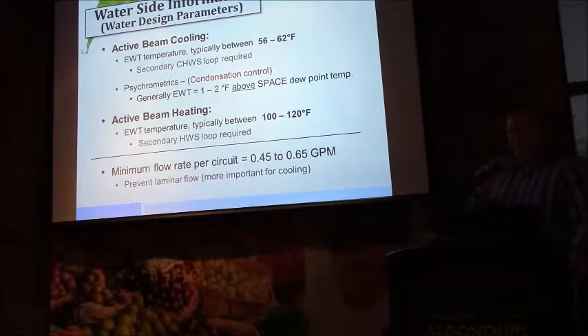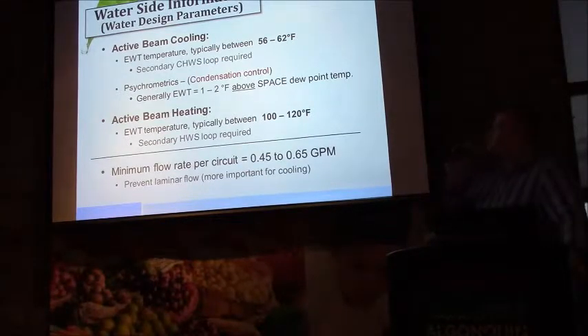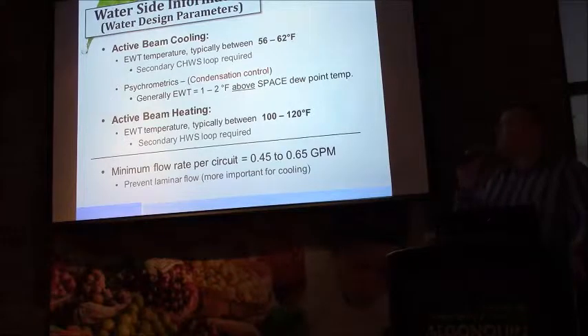Here's some operating temperatures that we see for the entering chilled water. Obviously, for a 56 degree entering water temperature, the space is being designed to something like 75 degrees Fahrenheit and 50% relative humidity. In many cases, if we look at that, it will preclude the use of an active beam for the space, given the mass flow that would be required to offset the latent load.